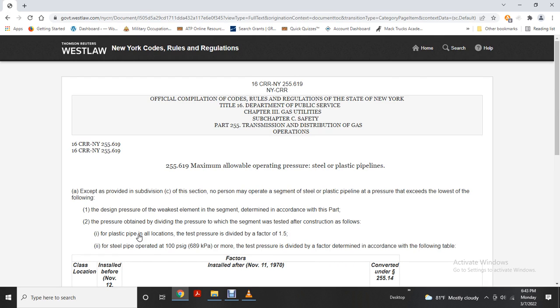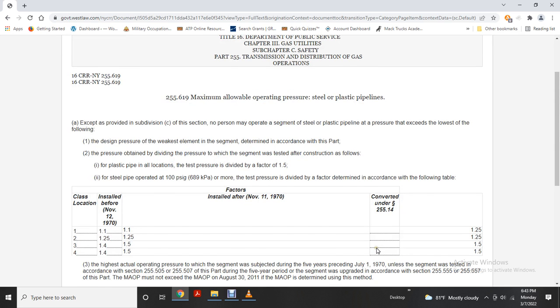Alright, maximum allowable working pressure for steel and plastic pipelines. Under subpart C, no person may operate a segment of steel or plastic pipeline at a pressure that exceeds the lowest of the following: the design pressure of the weakest element of the segment, determined according to the part. Or the pressure obtained by dividing the pressure to which the segment was tested by a factor: for plastic pipe, all locations, a test pressure factor of 1.5; for steel pipe operated at 100 psi gauge or more, the test pressure divided by the factor determined according to the following table.